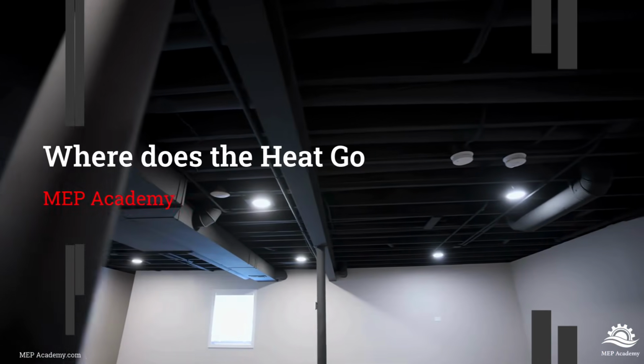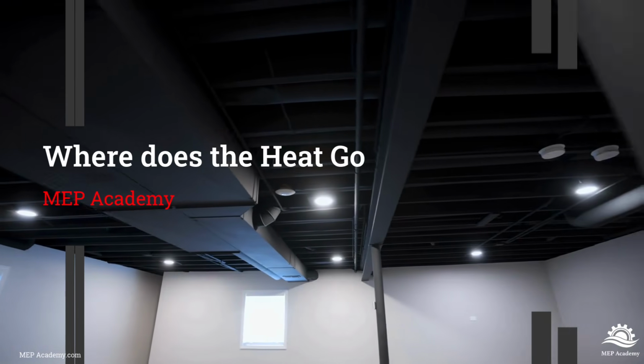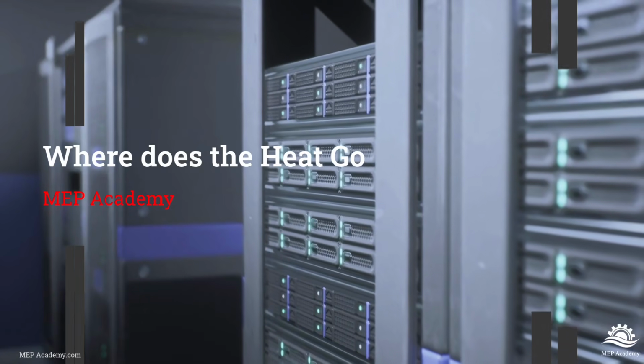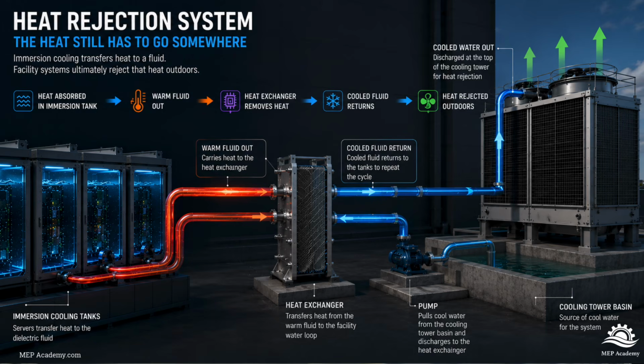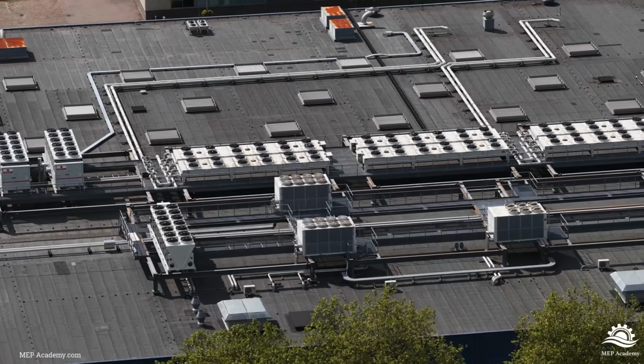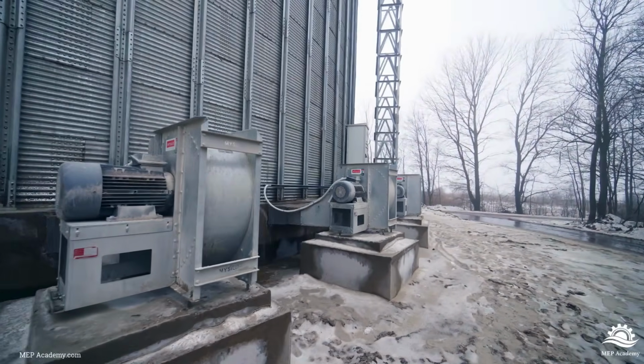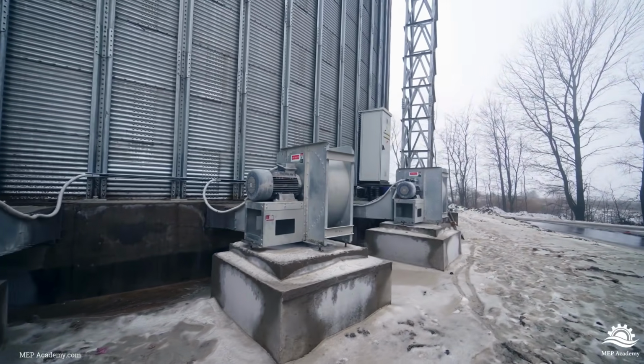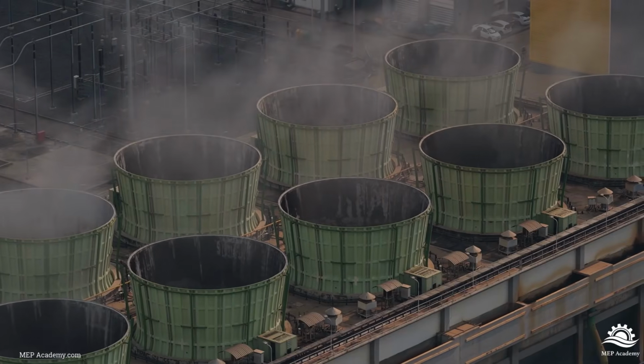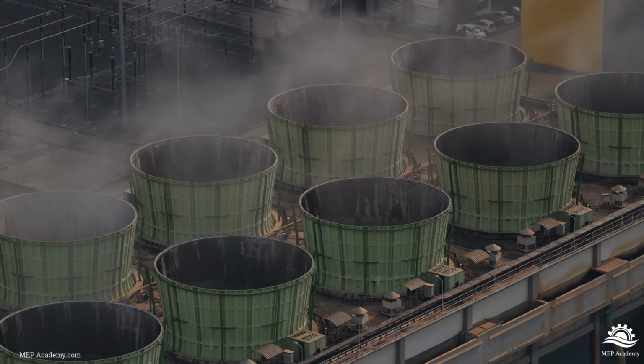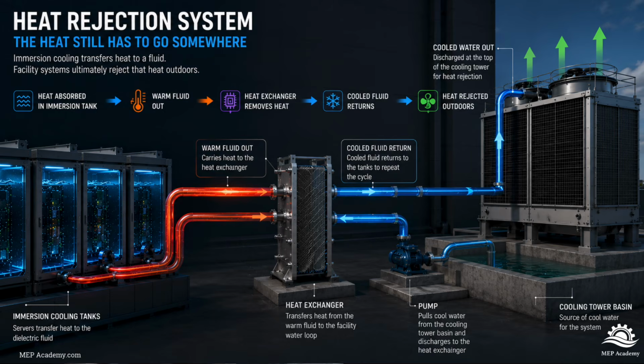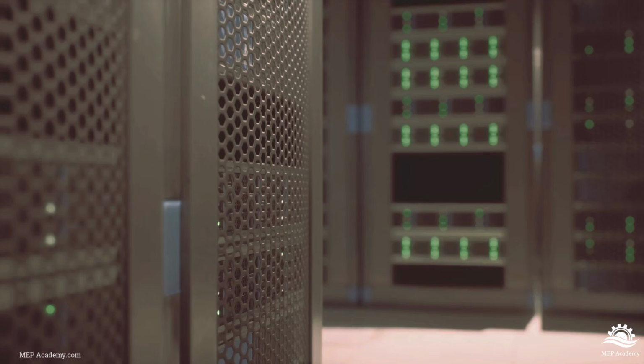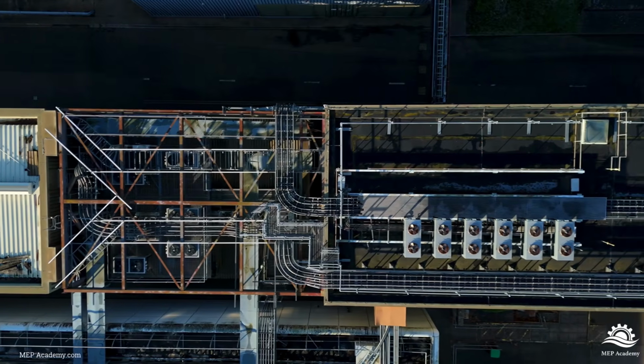A common misconception is that immersion cooling eliminates mechanical cooling systems. It doesn't. The heat still has to go somewhere. The only thing that changes is how we capture the heat. The heat still ultimately leaves the building through mechanical infrastructure. That may include chilled water systems, dry coolers, cooling towers, fluid coolers, or other heat rejection systems. The difference is that we're transporting heat with liquid instead of moving enormous amounts of air through a room. In many ways, immersion cooling simplifies portions of the data hall while shifting more emphasis onto facility water infrastructure.